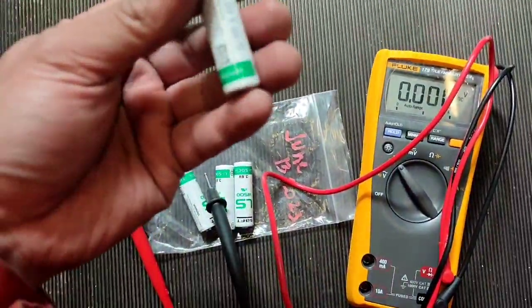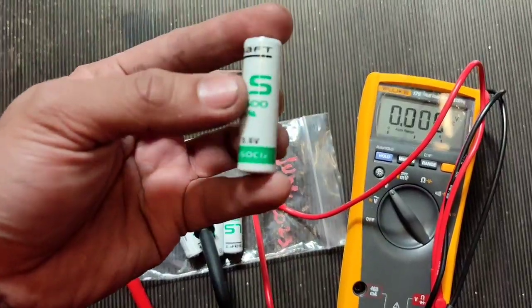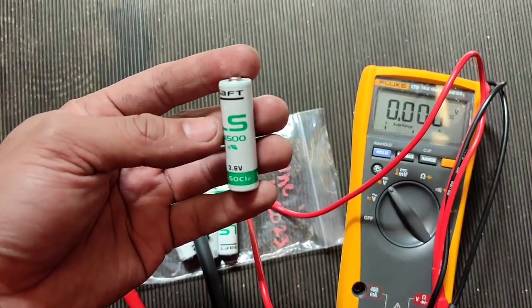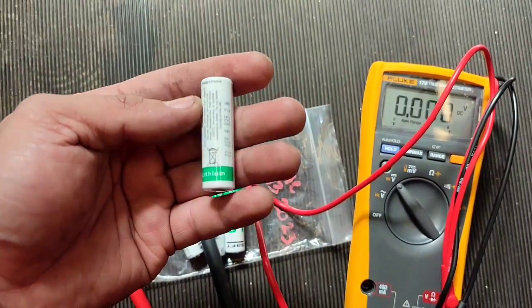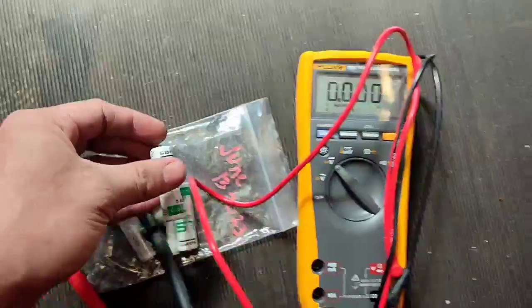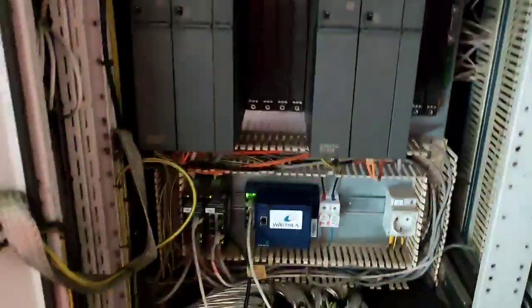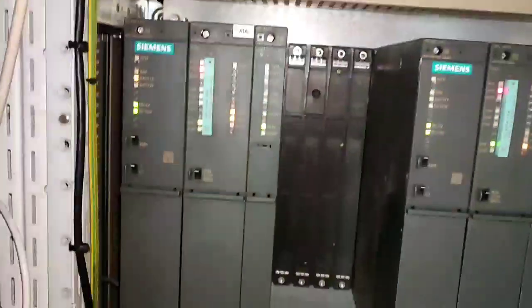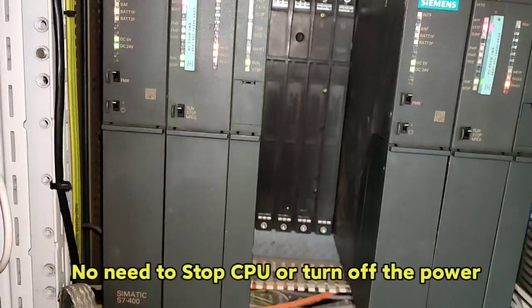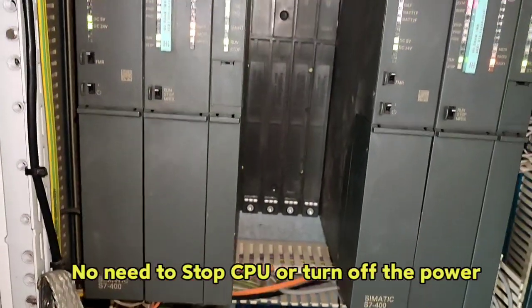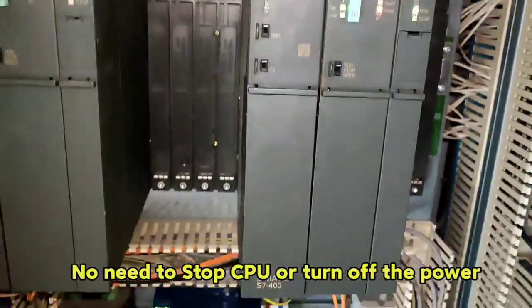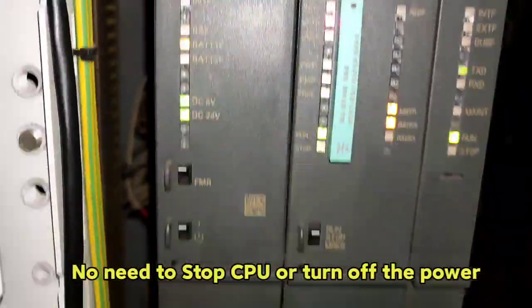Good day, this is about checking and replacing new batteries for our PLC - 3.6 volt lithium batteries for the Siemens S7-400. There is an alarm for number one, which means battery one is empty.